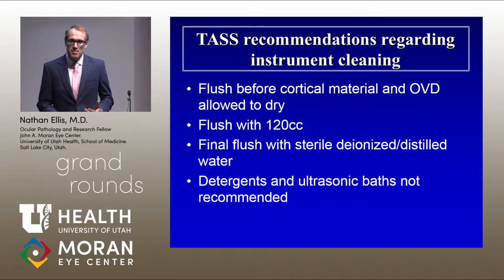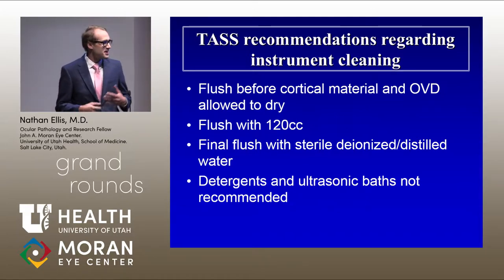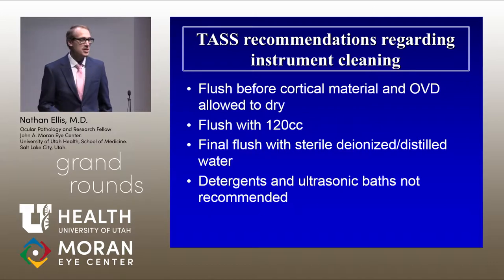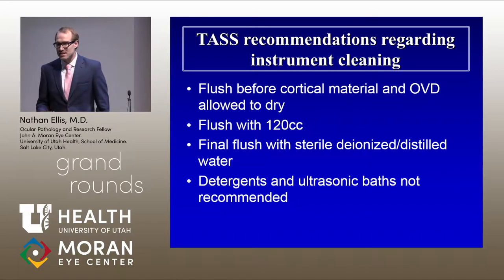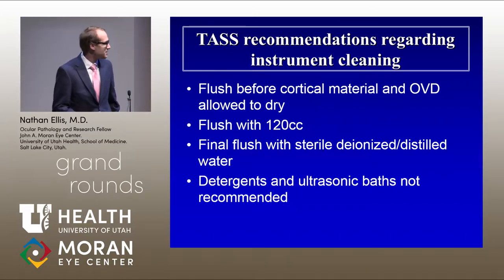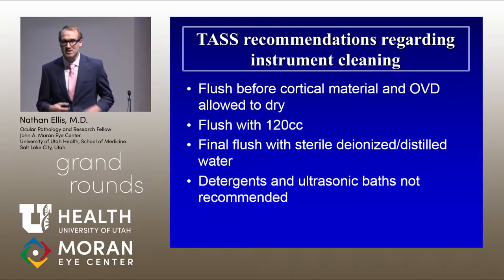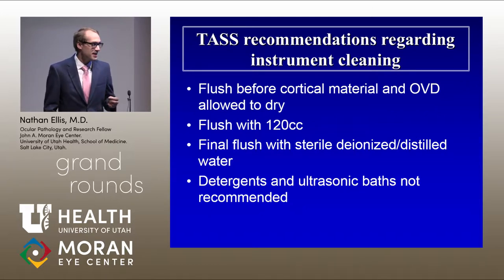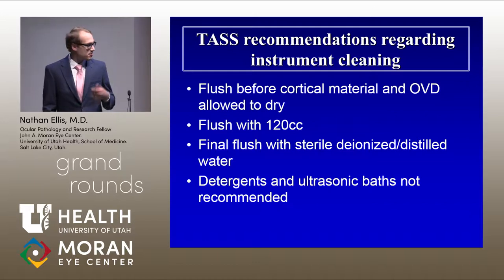The TASS Task Force makes recommendations for instrument cleaning. First, flush phaco and IA hand pieces as quickly as possible after surgery to prevent OVD and cortical material from drying, as dried material is very difficult to remove. Flush with 120 cc's of sterile deionized water. We recommend that the final flush be with sterile deionized distilled water to avoid ions being retained in the hand pieces during autoclaving. Tap water contains small amounts of gram-negative bacteria; while the bacteria are killed in the autoclave, the lipopolysaccharides and endotoxins in the cell wall are not.